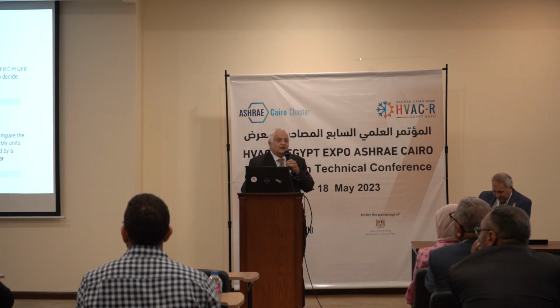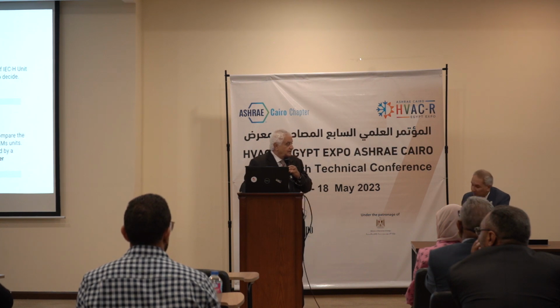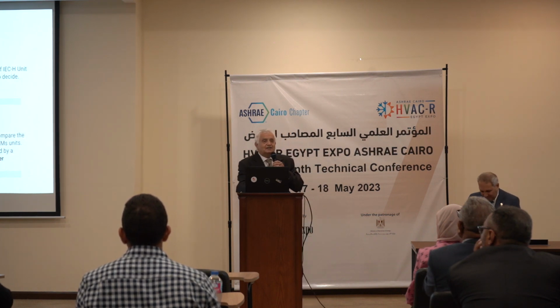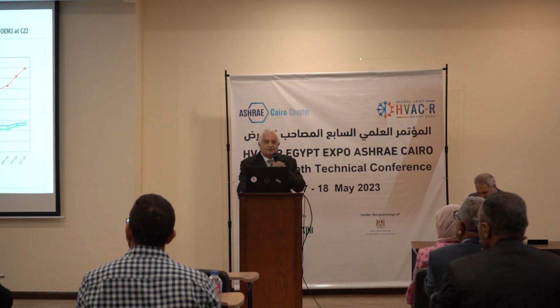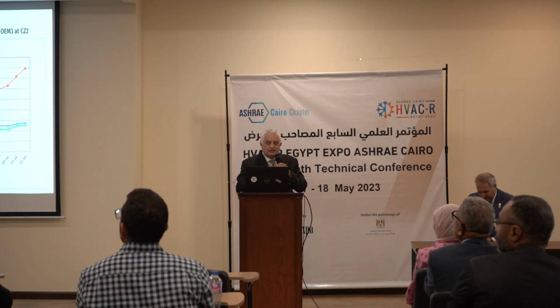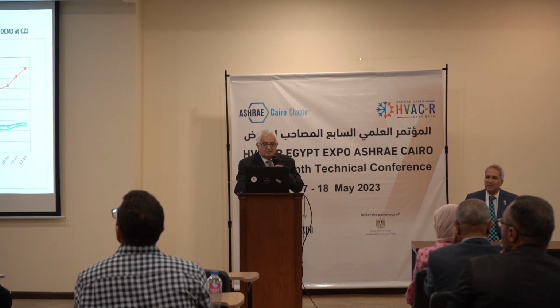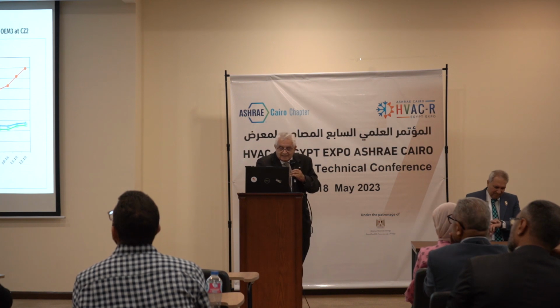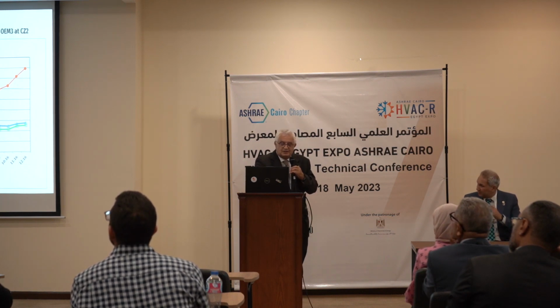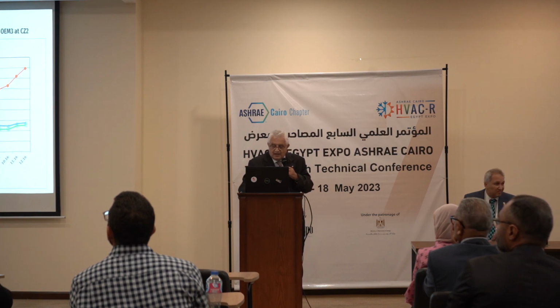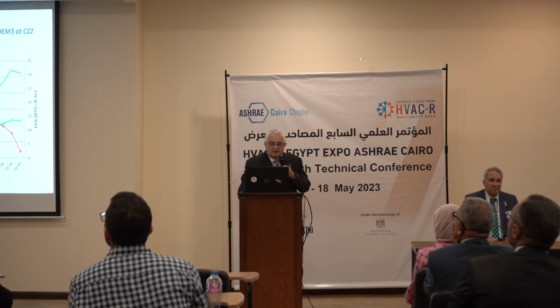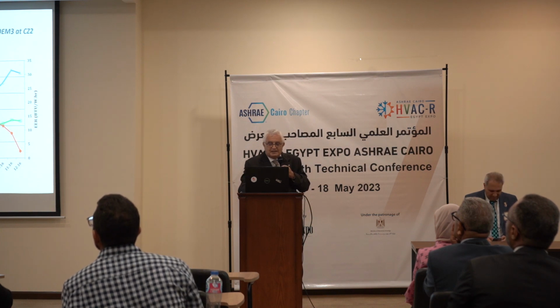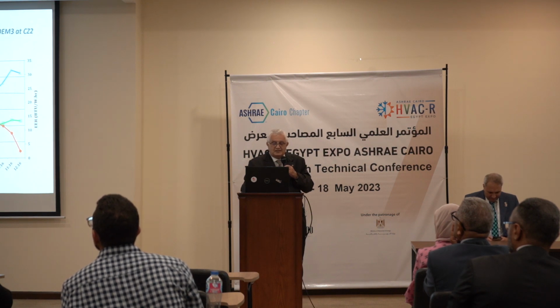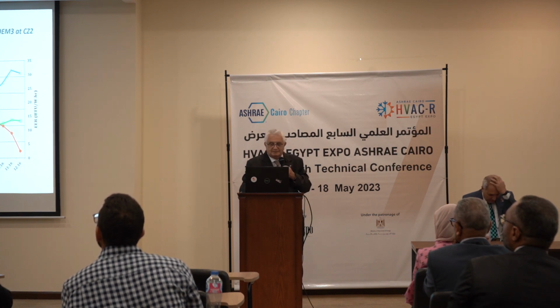To give you a very quick idea of what we got in the end, we have here graphs that show, the red point there shows us the dry bulb temperature and the exit temperature of the DX machine and the IEC machine. They are almost the same. And then here you see the different wet bulb temperatures, and the very important EER. The EER in blue is the EER of the IEC-H machine, and it's always higher than the EER of the DX machine, which is the whole idea.